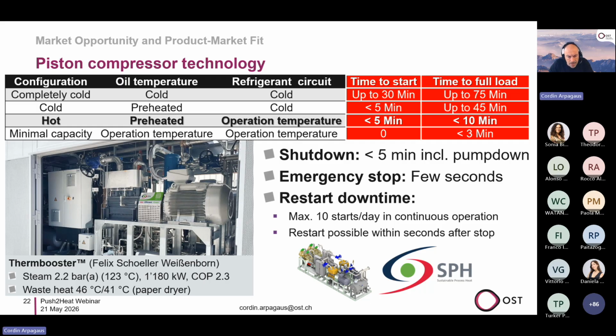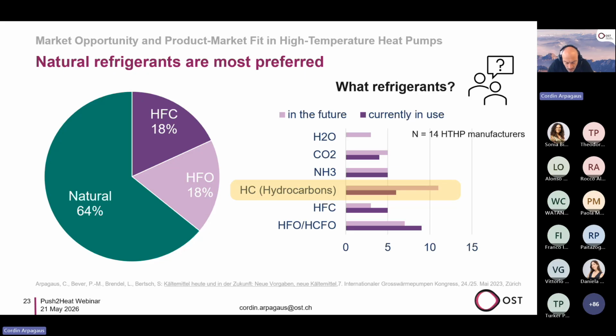So this is just an example of the thinking steps behind this product market fit tool. Another parameter is, for example, the refrigerant, and here we can see that the future looks like to go into natural refrigerants, especially for the industrial scale or industrial application, hydrocarbons, which offer high temperature applications. Then we have ammonia, CO2, water, and so on, and also HFOs. So if the heat pump that would be interesting for the customer offers natural refrigerants, that is an additional competitive advantage.